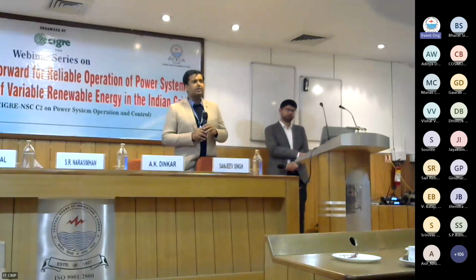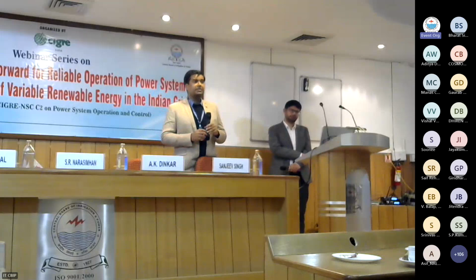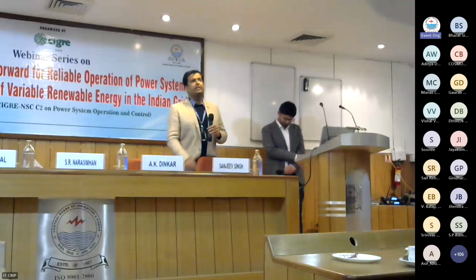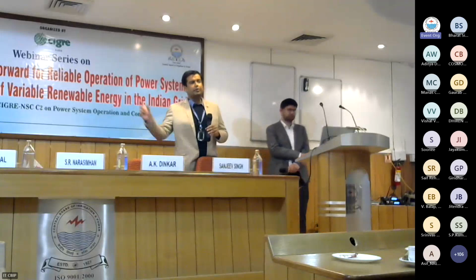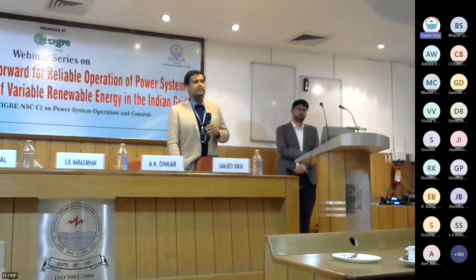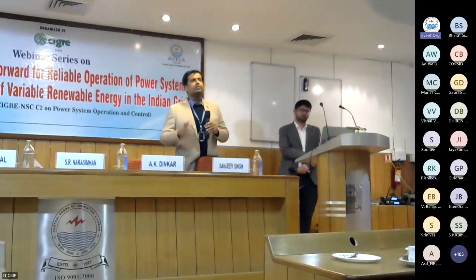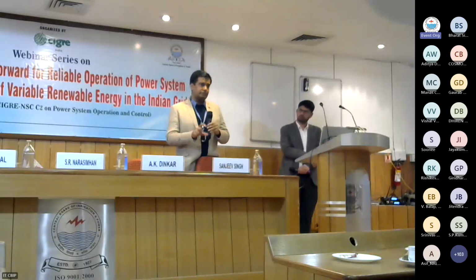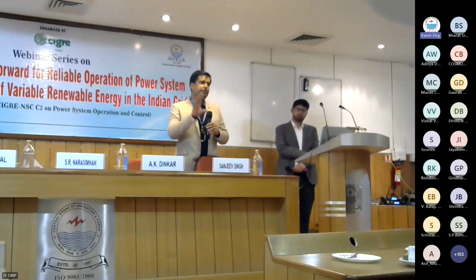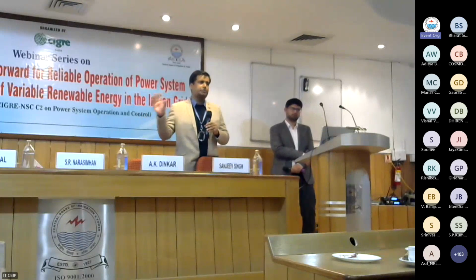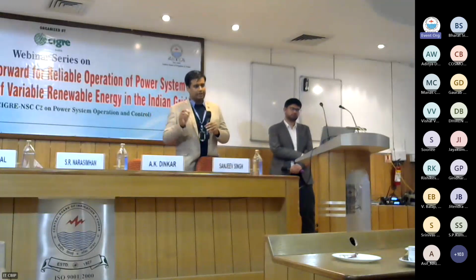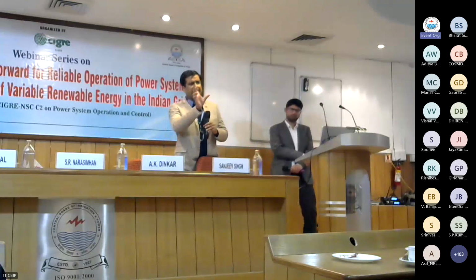So as of now, as mentioned in the presentation also, we do not have that high resolution data. When we are talking about harmonics, we certainly require millisecond accuracy data. From the PMUs, which are available at 40 milliseconds, it is very difficult to comment on them. Power quality based tests, which are mandated as per CEA standards, are time bound to be done at specific durations, specific intervals. It is felt that those are appropriate to cover the details because a 7 days time window is there in IEEE 519.